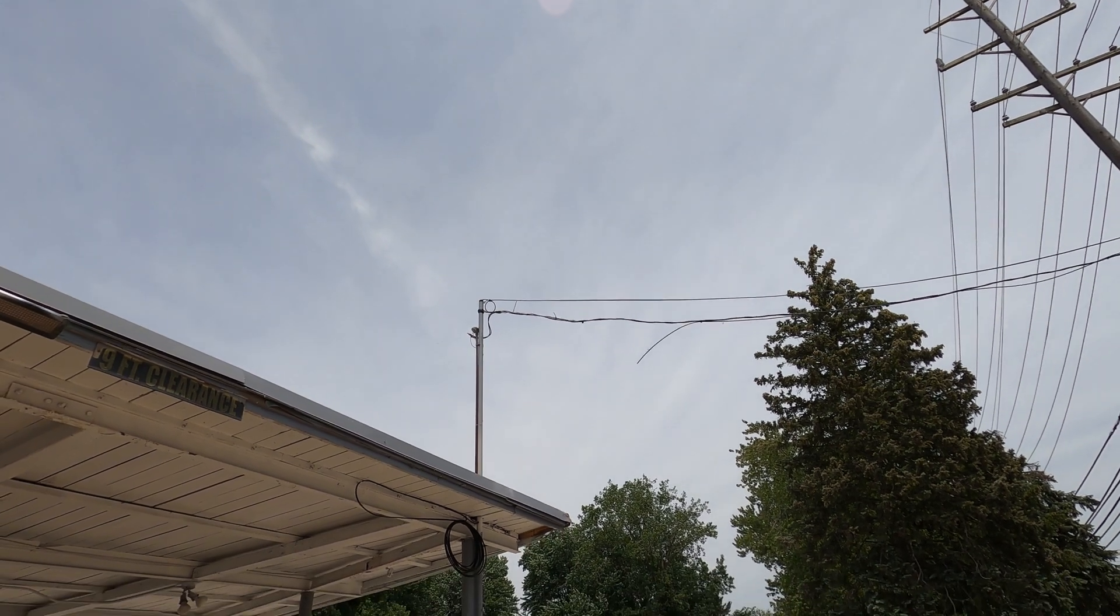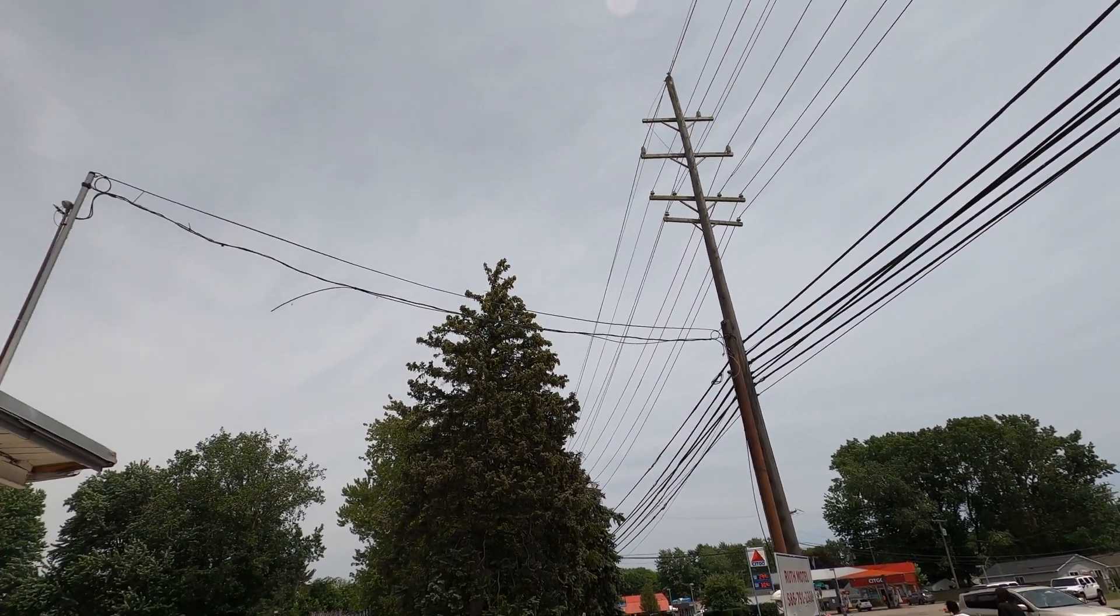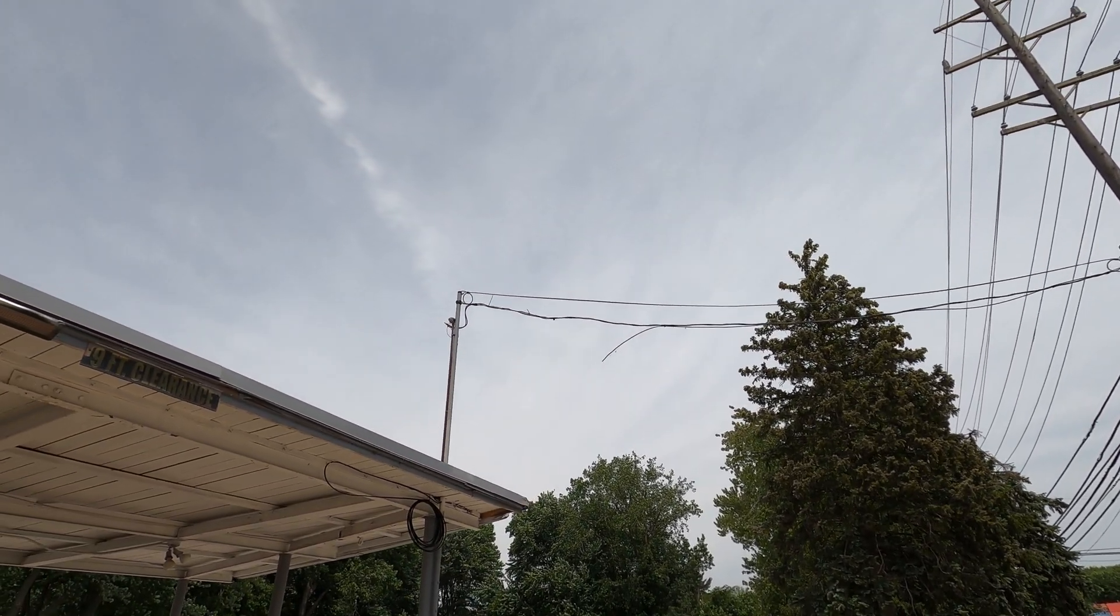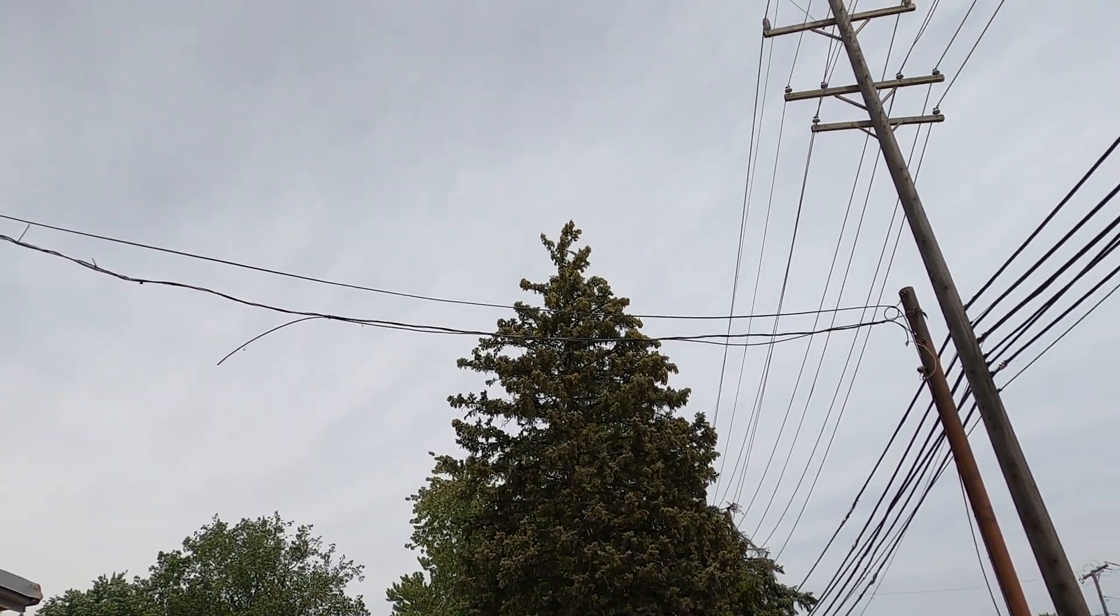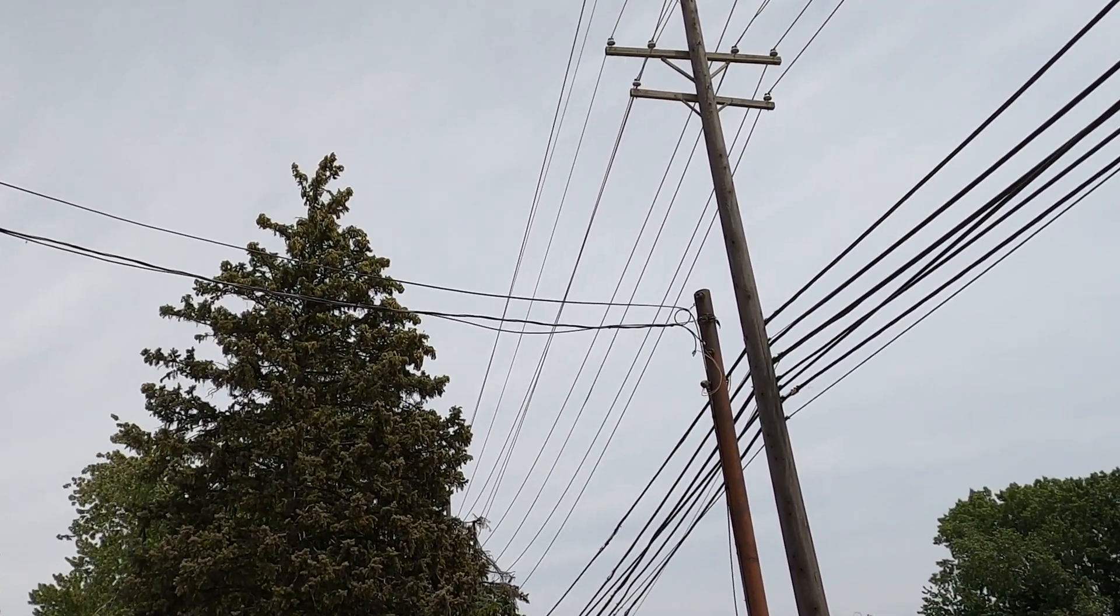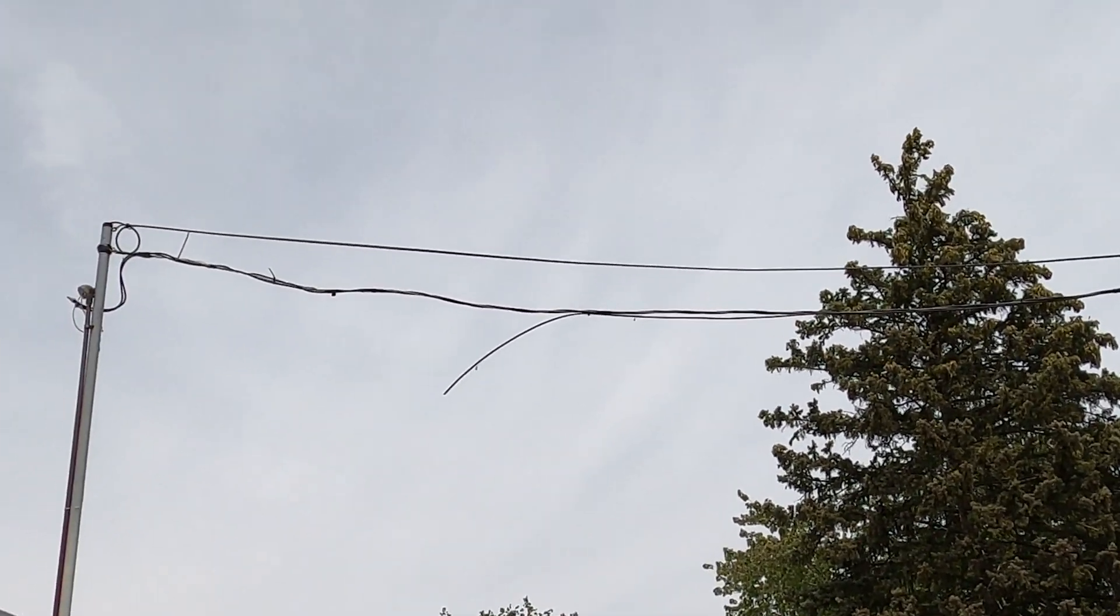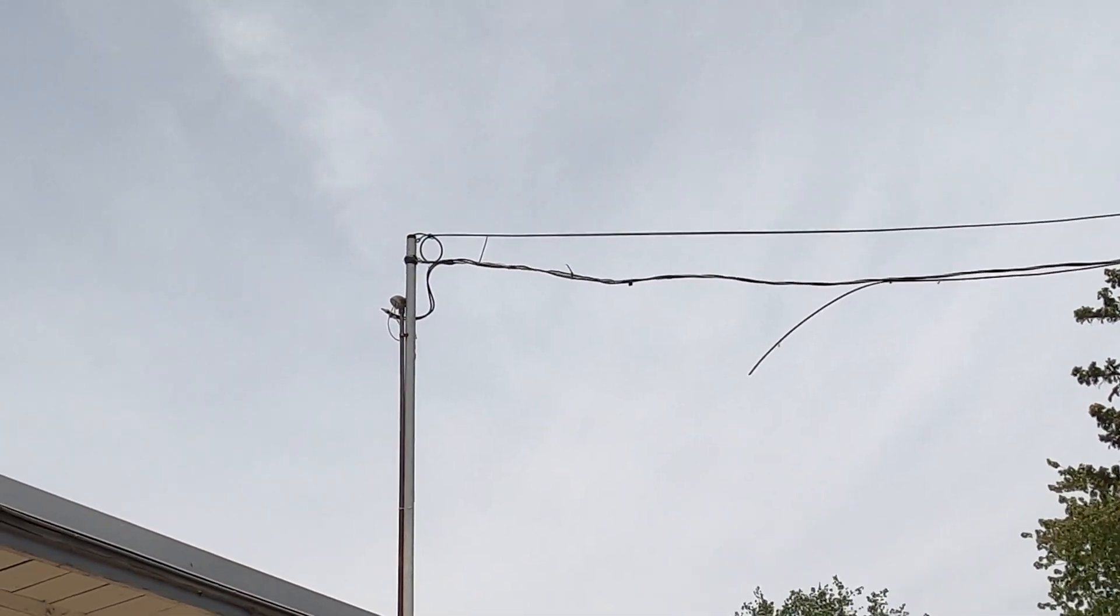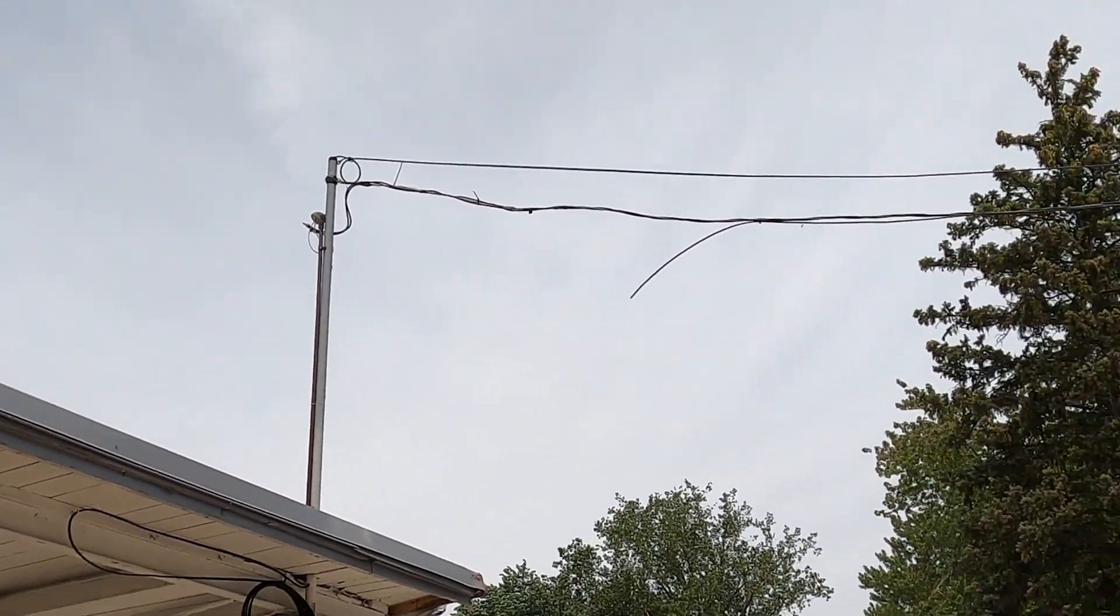So there it is, the completed messenger run going from pole to pole all attached. And if you'll notice, there's an electric wire several inches below the shielded ethernet, which is critical to have shielded ethernet and maintain at least a two inch separation. But I decided to take it safe and I've got about a six to eight inch separation going there. So that's pretty much it.